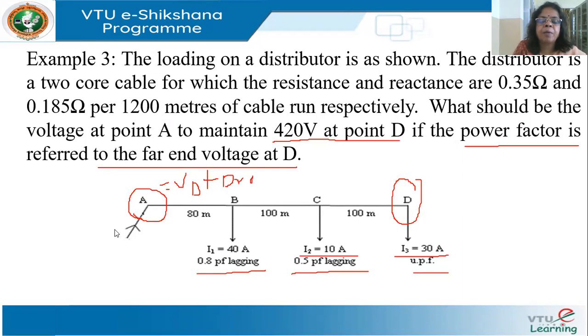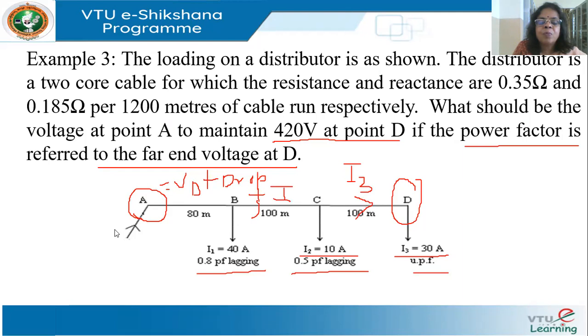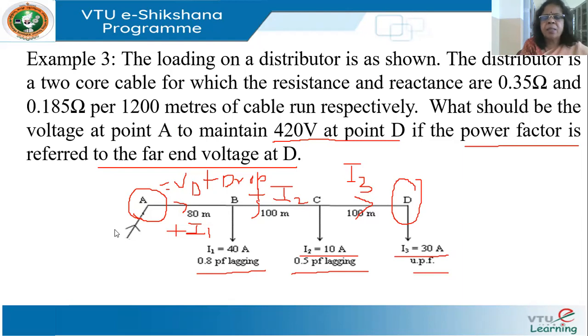You know why this is called a distributor? Because I have tappings in between. If it's a feeder, I will not have tappings. The current in section CD is I3, in BC it is I2 plus I3, and in AB it is I1 plus I2 plus I3. I have to determine what is I1, I2, I3 and the impedances of these sections, find out the voltage drop in them, add it to the receiving end voltage, and I will get VA.